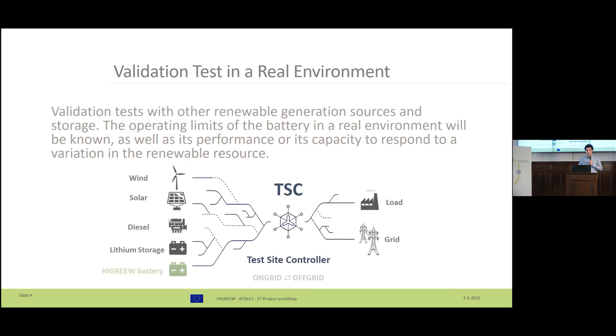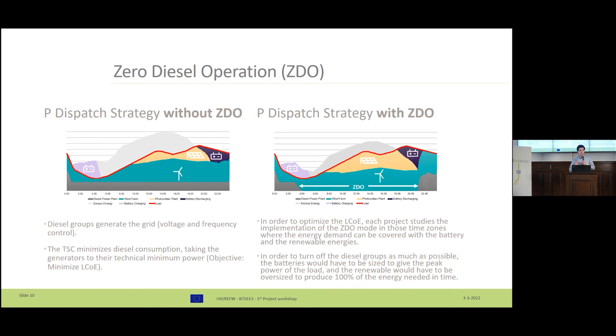This slide is about zero diesel operation, a special off-grid mode that tries to maintain the grid only with batteries. So it's one of the most demanding modes for the batteries. We think flow batteries are a perfect technology to test with this mode because you can separate the energy and the power, so you can reduce the cost of the battery. On the other side, you need to maintain the quality of the grid and the performance of the battery. So the control of the battery, the BMS, for this mode is highly demanding.